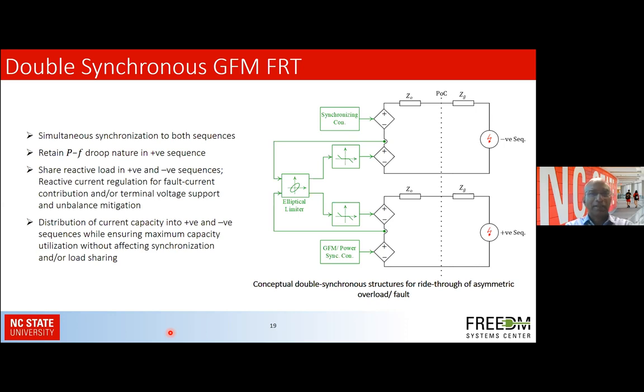And for the reactive current regulation for fault current contribution, terminal voltage support, and also for unbalance mitigation, both the positive sequence and the negative sequence components could be utilized. So the distribution of the current capacity into positive and negative sequences is needed, while ensuring the maximum capacity utilization of the inverter, not exceeding its absolute overcurrent limits, and also without affecting synchronization and/or load sharing. So this is ideally what we would want.